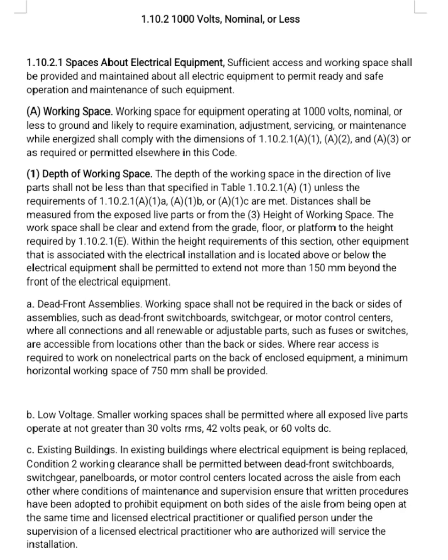1.10.2 1,000 volts nominal or less. 1.10.2.1 Spaces about electrical equipment. Sufficient access and working space shall be provided and maintained about all electrical equipment to permit ready and safe operation and maintenance of such equipment.